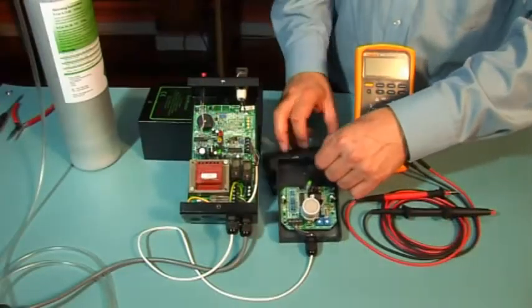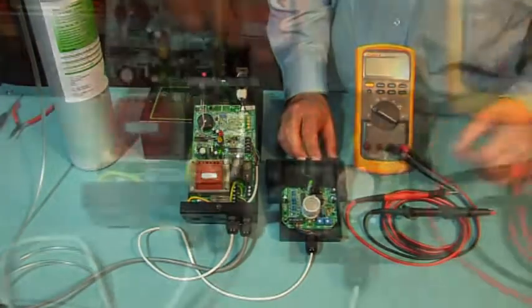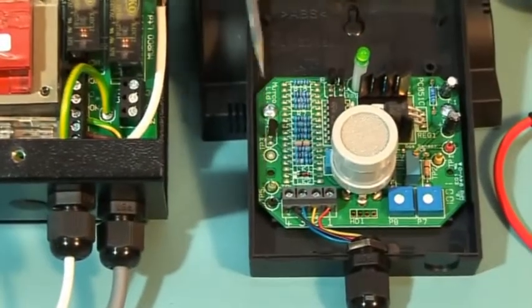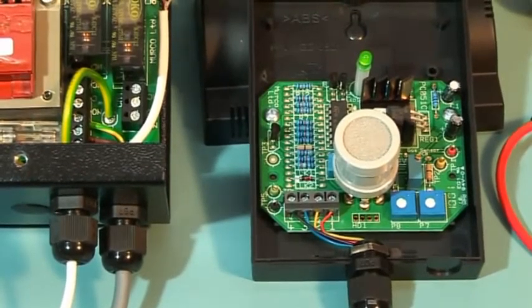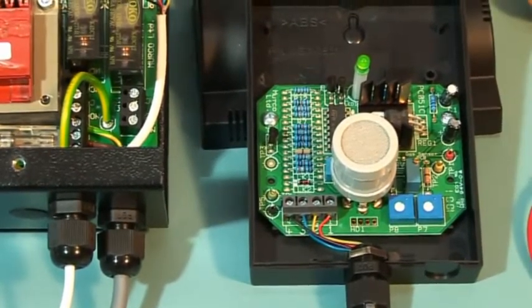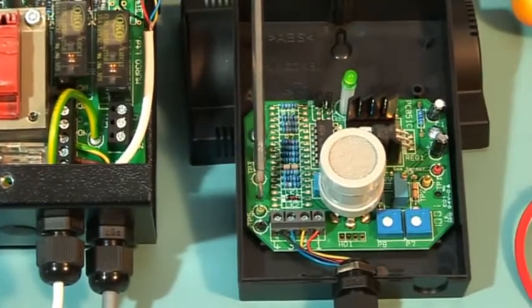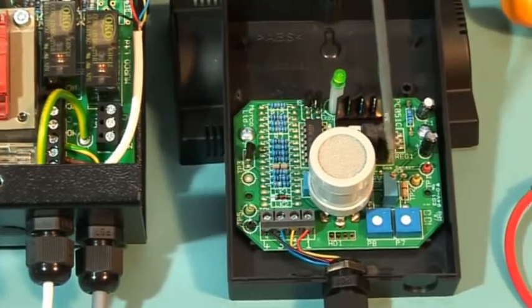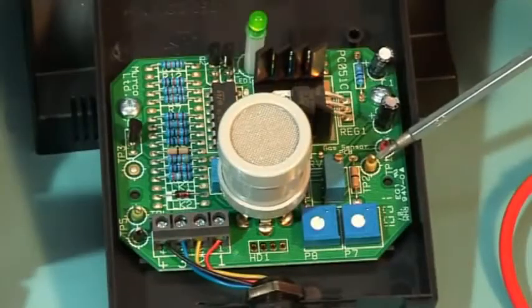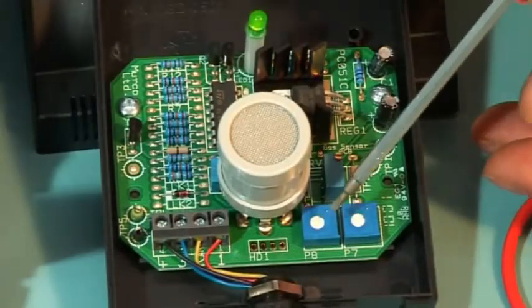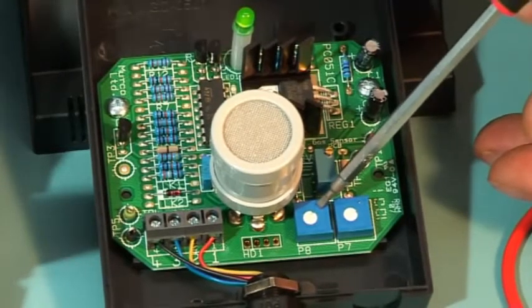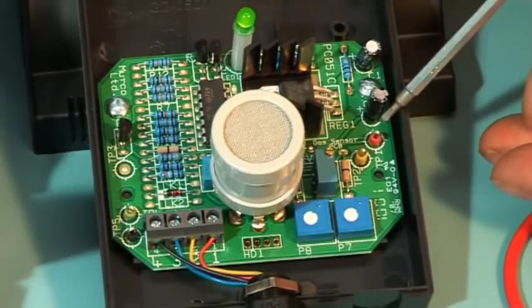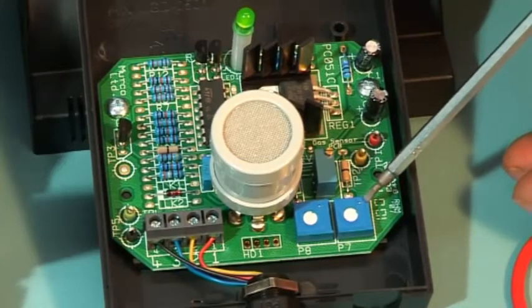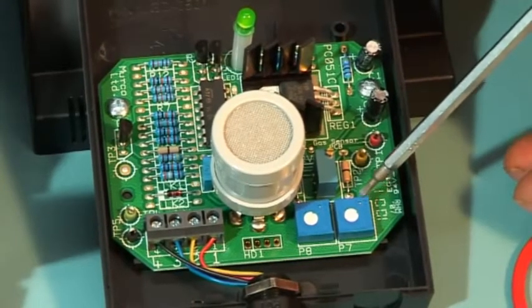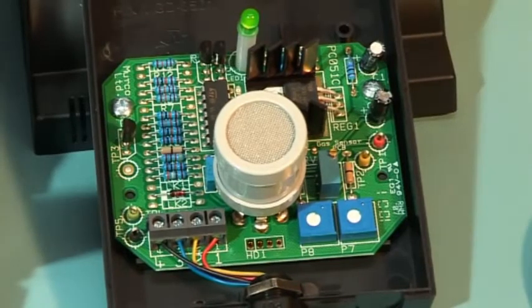For the 2-level systems, monitor the ground or 0 volts at TP5 on the sensor PCB. The standby voltage output in clean air can be monitored at TP4 and can be adjusted using RV1. The low-level alarm can be monitored at TP2 and adjusted by P8, and the high-level alarm can be monitored at TP1 and adjusted by P7. The delays for the low and high level are fixed and cannot be removed, but are approximately 25 seconds after reaching the alarm set point.